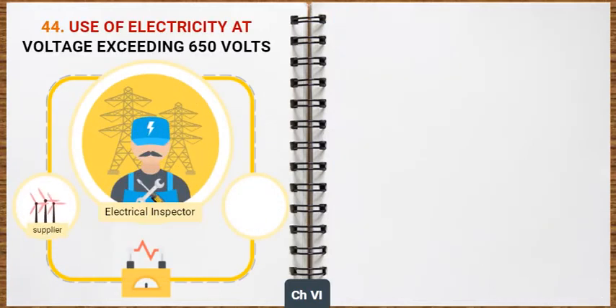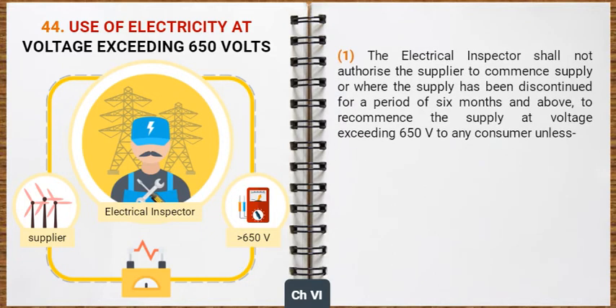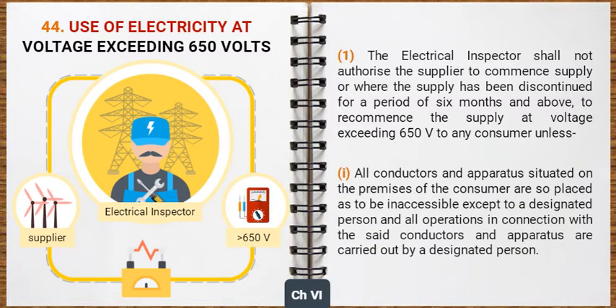Now, let us learn about the safety provision related to use of electricity at voltage exceeding 650 volts. The electrical inspector shall not authorize the supplier to commence supply or where the supply has been discontinued for a period of 6 months and above to recommence the supply at voltage exceeding 650 volt to any consumer unless all conductors and apparatus situated on the premises of the consumer are so placed as to be inaccessible except to a designated person, and all operations in connection with the said conductors and apparatus are carried out by a designated person.